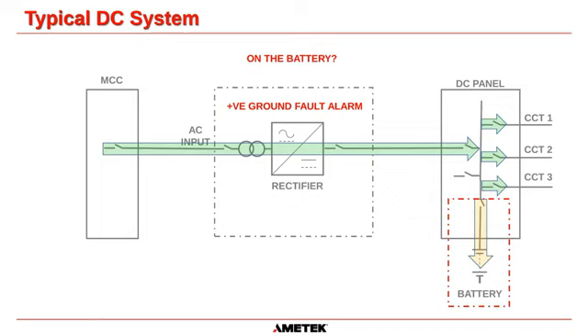Okay, if you open this breaker and the ground fault remains, then we know it's one of these 3 circuits. Absolutely guaranteed. Okay. Now, a lot of people say, well, why would a battery go to ground? Well, remember that I said that the battery is always sitting on a battery rack. The 2 things that I've seen happen that create a battery ground fault is either there's a leak in the jar of a wet cell battery where the electrolyte leaks down and somehow gets to the metal of the battery rack. Okay, and then that gives a conductive path between the internal of the battery down to the ground of the battery rack, and that will give you a ground fault alarm.